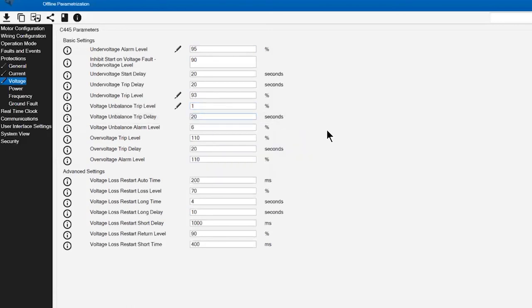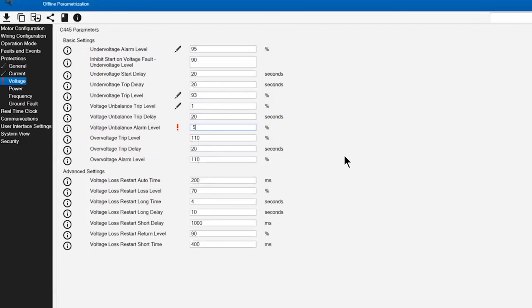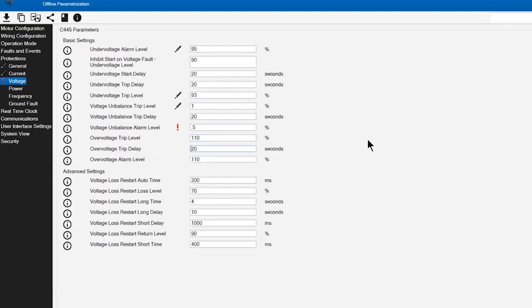Trip delays are subjective. I generally will stick with defaults in association with the protective functions that I'm setting. We do want to set an early warning alarm level that would give us indication prior to reaching trip level, and that's a 0.5%. Those are some easy ways through this software app that I can make a couple of small changes and really extend the reliability.